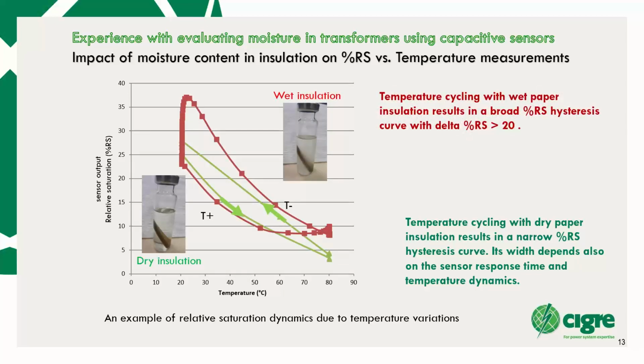And I would like to explain this curve. What happens here? First of all, we have an increase of temperature. That means that the moisture which is in the solid insulation goes into the oil. Oil which is hot can dissolve more moisture than cold oil. That's why the relative saturation is actually decreasing, as we see here on this arrow.